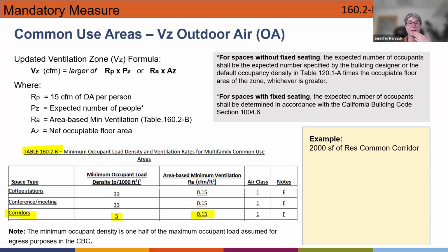So in this case, I gave you the formula, and then I'll give you an example. If we look at corridors, it has a minimum occupant density load of 5 people per 1,000 square feet. And then it gives you your area-based minimum ventilation rate, which really has not changed much from the 2022 code. So for the most part, your answers are going to be very similar to what you had in the 2022 code anyway.